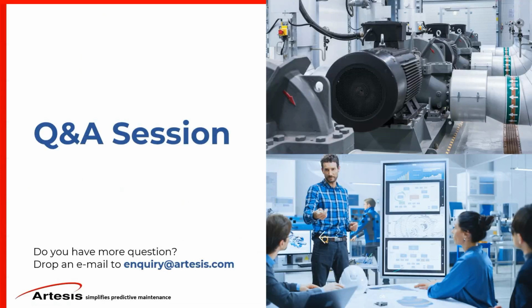Yes, this is machine learning. AI is a term that is used very loosely nowadays. We don't want to use the term AI, but we use machine learning, because when the system is first installed, it creates a digital twin of the whole system, and then it detects the existing faults. Afterwards, it keeps monitoring the deviations from that learned model. That is machine learning, and that process takes 7 to 10 days. I must also emphasize that.